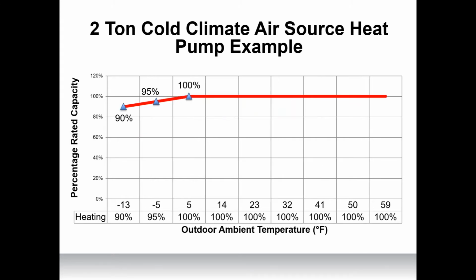Now let's take a look at the heating capability of a 2-ton VRF cold climate air source heat pump. This heat pump maintains 100% of its heating capacity down to 5 degrees and still maintains about 90% of its heating capacity at -13. Please note these are all ambient temperatures, as wind chill has no effect on the heat pump's performance. So this is -13 ambient air temperature. It may be -40 wind chill for all I know at -13, but this is only looking at ambient air temperature. What happens if it gets colder than -13? The heat pump will continue to operate, just at a lower capacity. So we're going to see that derate continue on beyond -13. I personally would be 100% comfortable installing this cold climate heat pump as my primary heating source here in Chicago. At -13, I'm getting 90% of my heating capacity. As long as I sized my system appropriately, I would feel comfortable with this as my primary heat source here.